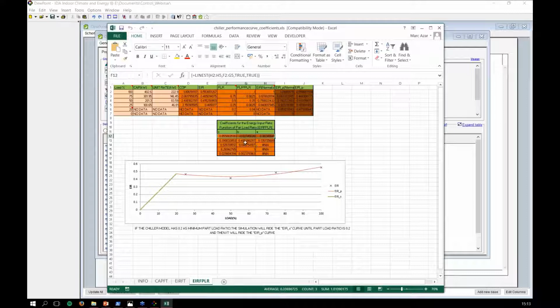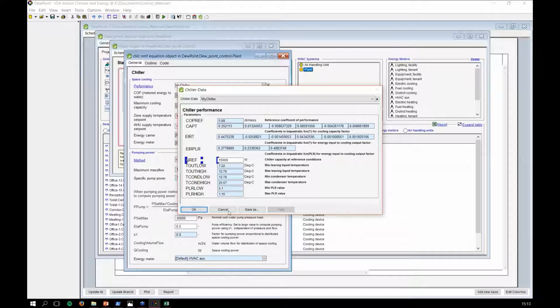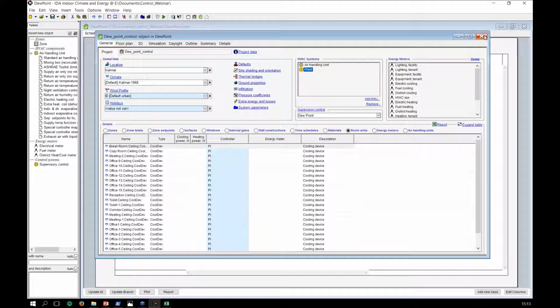And I changed the sizing of it. I already did my cooling load calculation and I know the capacity, so I put there 15,000 watts. That's the only thing I changed there. So that's my base dew point temperature control. I'm keeping 1 degree above the dew point, and I have a realistic COP on my chiller. That's all I did.